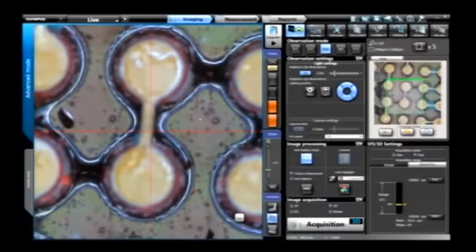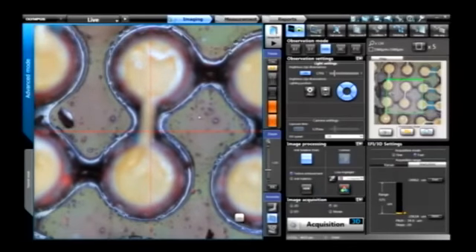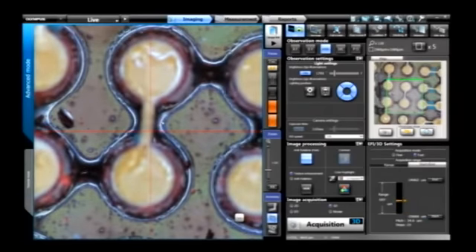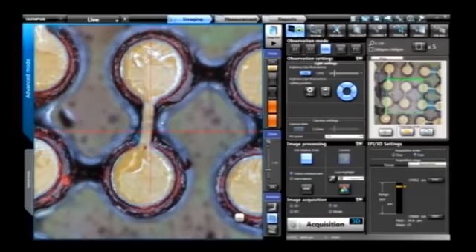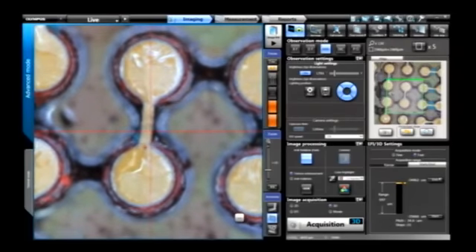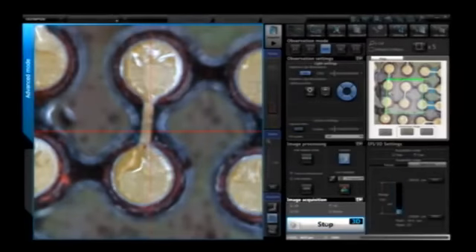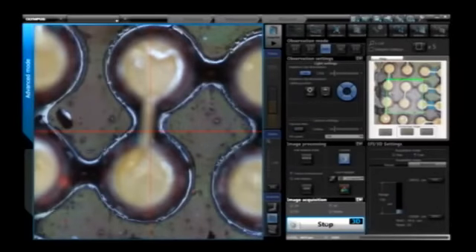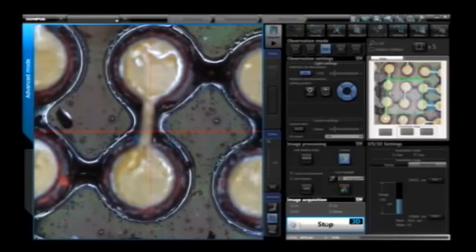To set up a 3D image, really all we have to do is focus down to the bottom. And I'm focusing with the scroll wheel on the mouse. You could also use the focus buttons here, but you just hit start at the bottom of focus, and then you go to your very top of focus. This would be the top of these pads here. Okay. And you hit end on that, and then you hit acquire, and it's using our image processing technique, any of our observation modes, and it automatically captures this all-in-focused image for us.